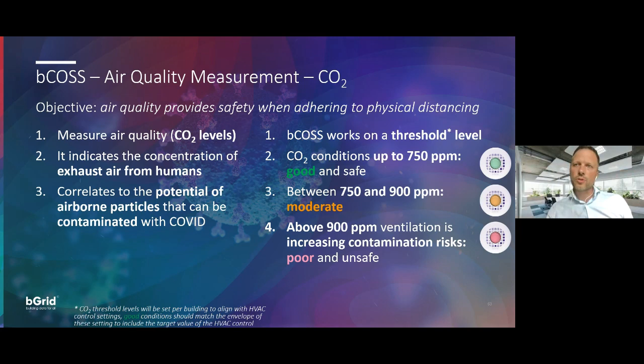We do the same for air quality. We measure CO2, which directly correlates with how much exhaust air there is from humans, which correlates to airborne particles that can contaminate you with COVID. Good conditions are up to and including the control envelope of the HVAC system. If it surpasses that bandwidth, it turns moderate, and when it shoots through to like 900 ppm, it turns poor. You'll be surprised how quickly that happens even in modern high-end offices. Again, these are visible throughout the 3 layers.